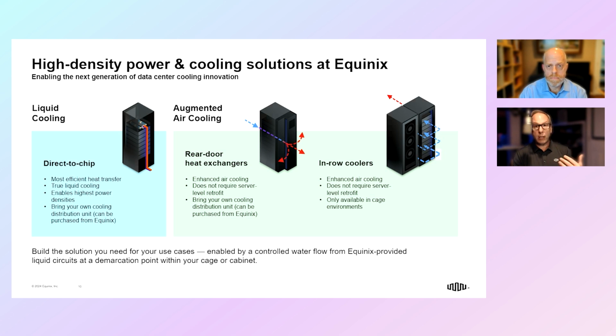At Equinix we think direct-to-chip cooling is the most efficient of the three options, especially for customers looking to handle high-density workloads like the 9680s you were speaking about. The increased density and cooling efficiency make it the best place to start. But if you're not ready for dedicated liquid cooling, for budget or time reasons, our enhanced air cooling options like rear door heat exchangers and in-row coolers are absolutely available and accepted globally.